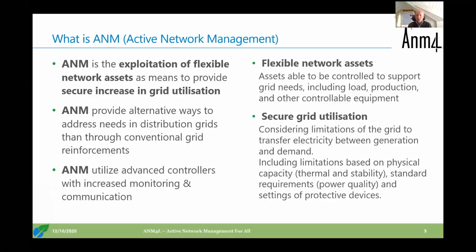The intention is to increase grid utilization, but it has to be done securely, considering the different limitations the grid has. Our focus is on the transfer capacity between generation and demand, where we have limitations on physical capacity related to thermal limits, as we just heard from a previous speaker on transformers, but it can also relate to stability. We also have standard requirements relating to power quality, with our focus on the amplitude of voltage, and we have protective devices in the system that need to be considered in this kind of development.